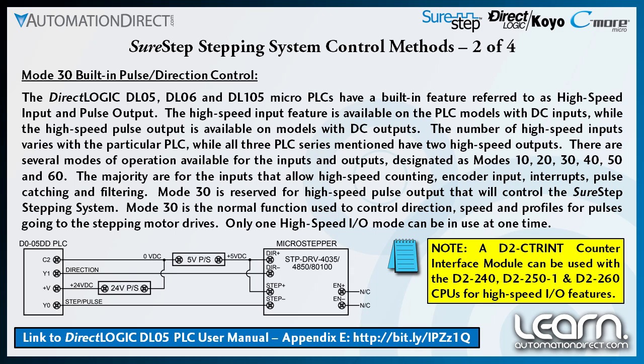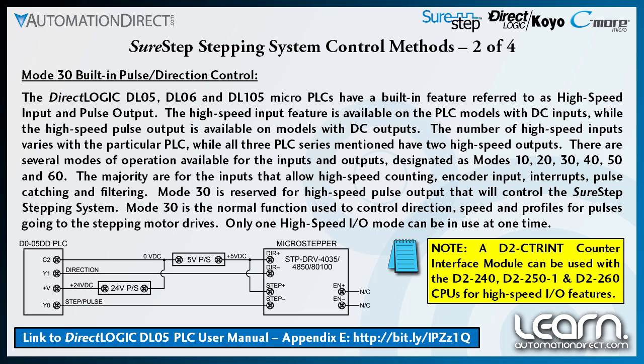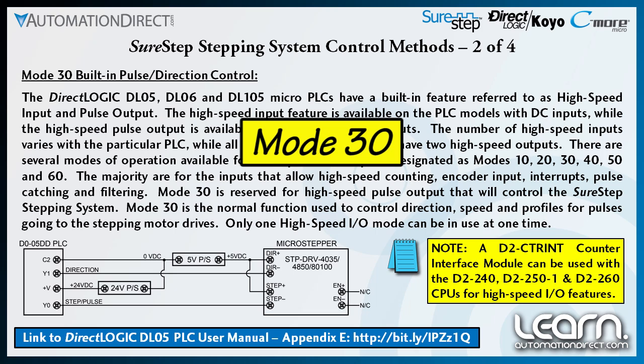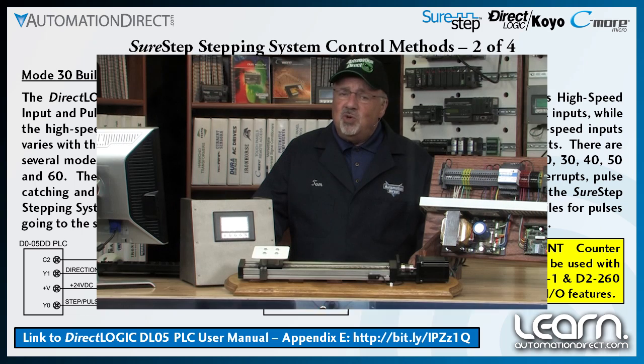The number of high speed inputs varies with the particular PLC, while all three PLC series mentioned have two high speed outputs. The modes of operation available for the inputs and outputs are programmed and designated as modes 10, 20, 30, 40, 50, and 60. Mode 30 is used to provide the pulse and directional signals from the PLC that would be used by the SureStep stepping system. Also be aware that only one of the modes can be in use at a time.